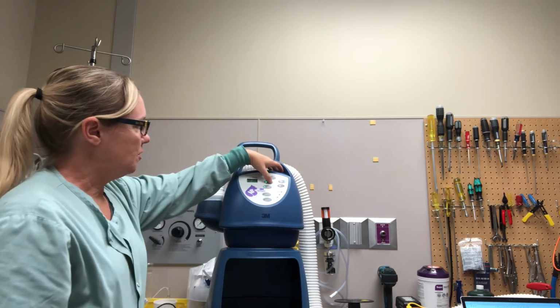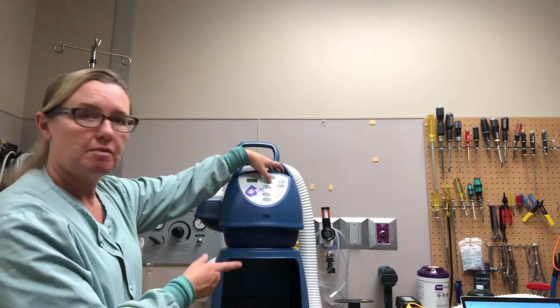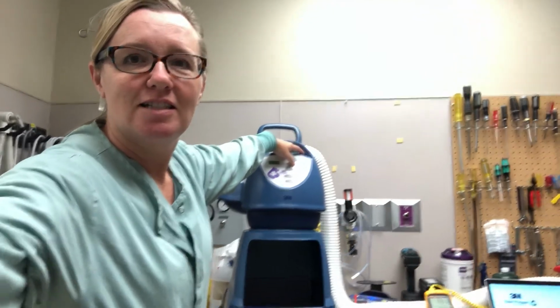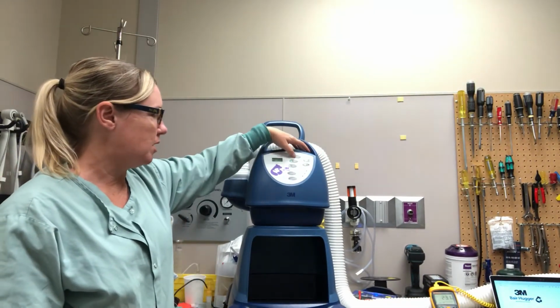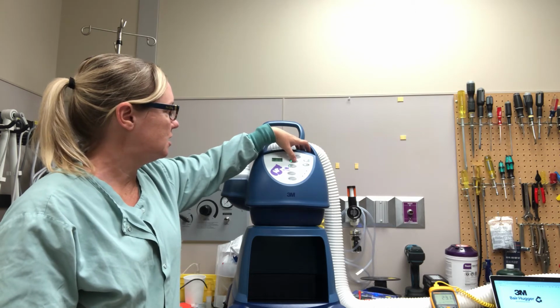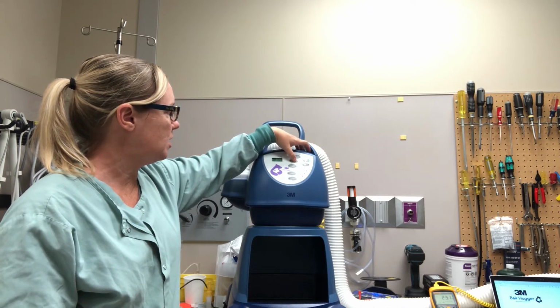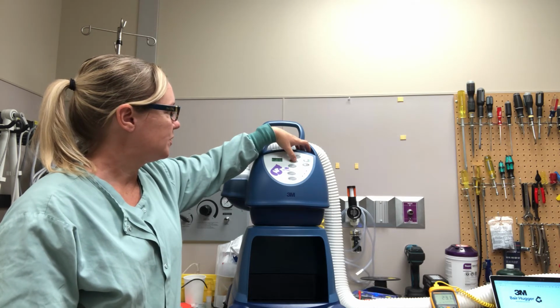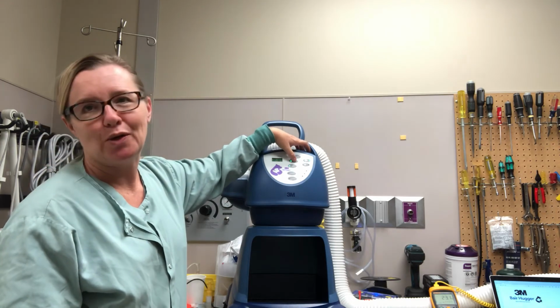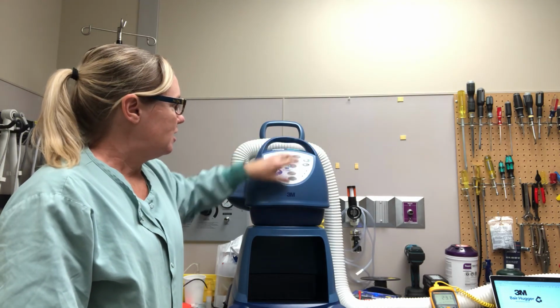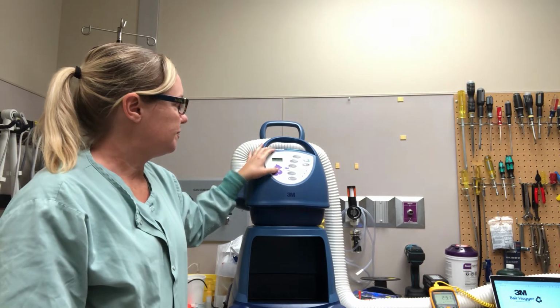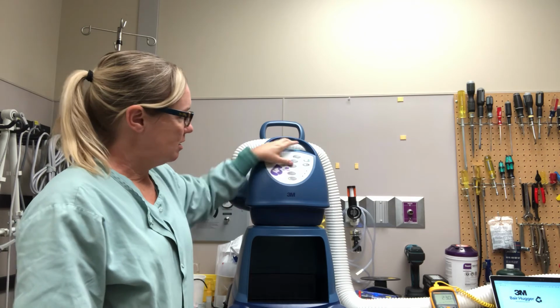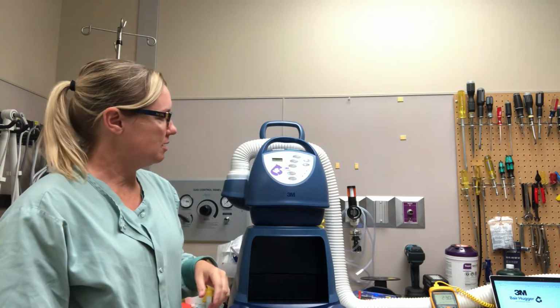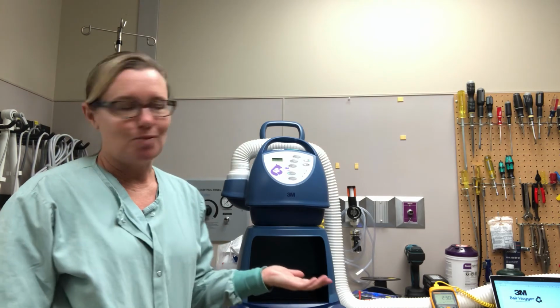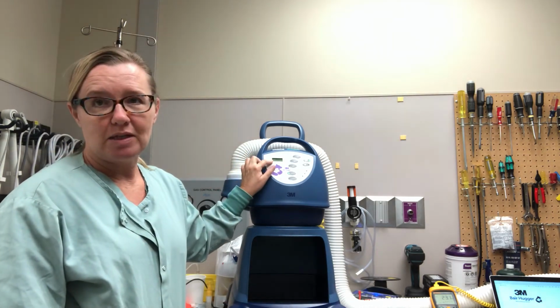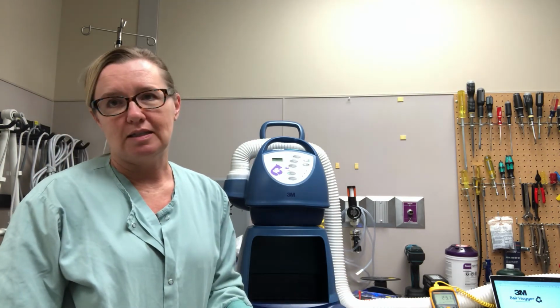Okay, so I need to increase this temperature to match my meter temperature, which is 23.1. So I'm just going to increase this till I reach 23.1 or close to there. Okay, so I'm about there. I'm at 23.0, which is close enough. And then to get out of this, I'm going to hit the Bair and I go back in standby. So now, when I press ambient, I go back into regular ambient operating mode, and I have 23 degrees Celsius on my screen, and I have 23.1 degrees Celsius on my meter.